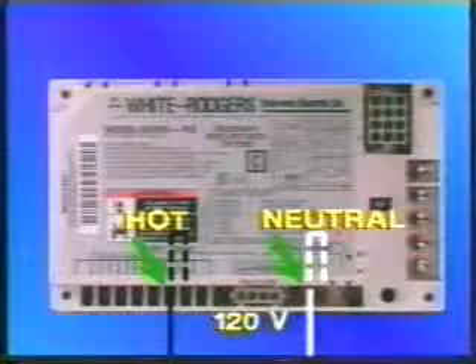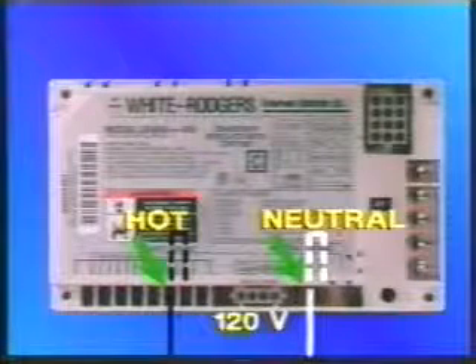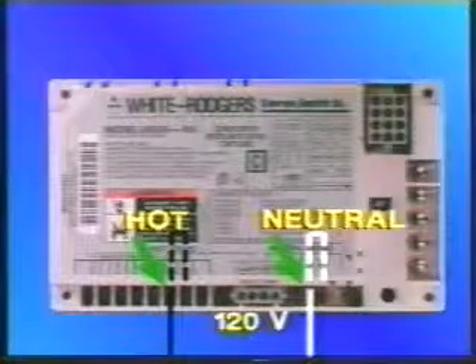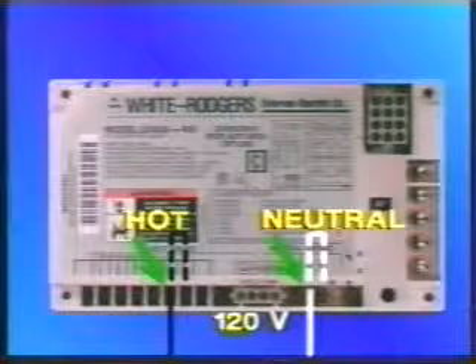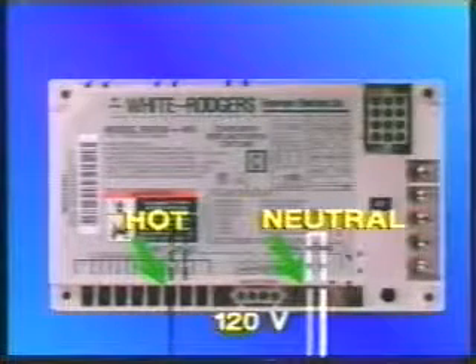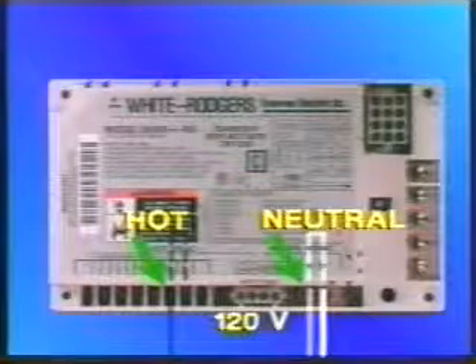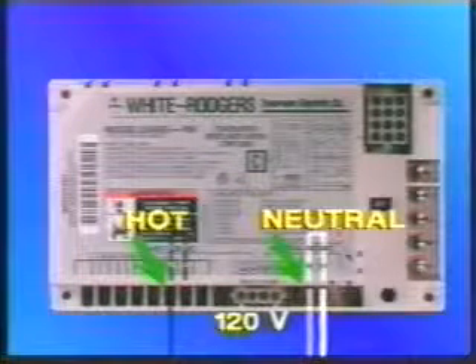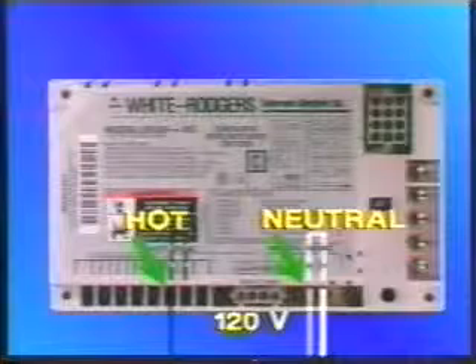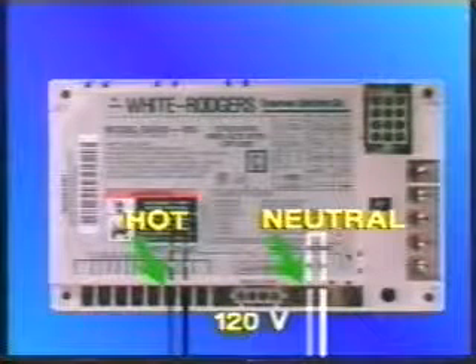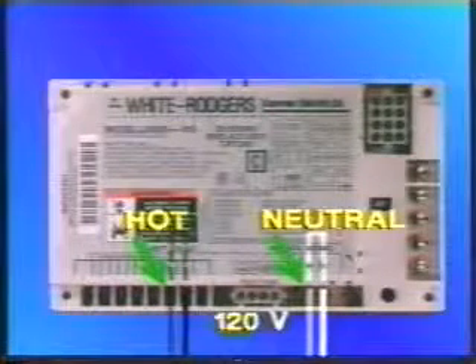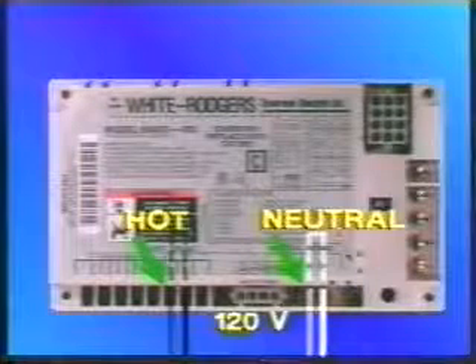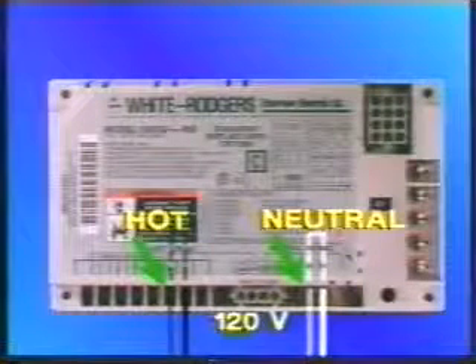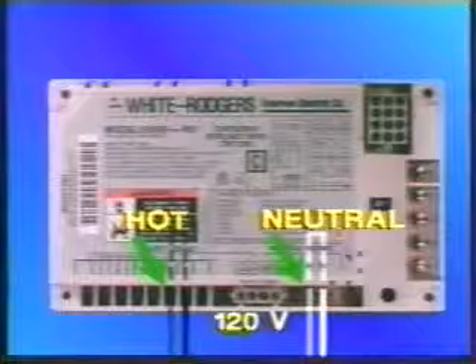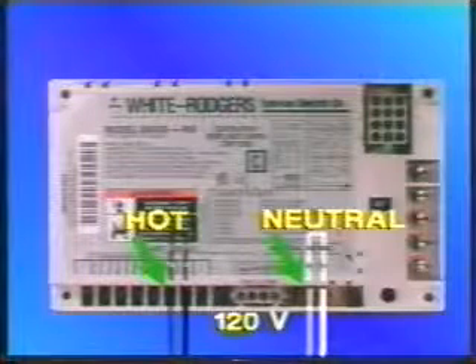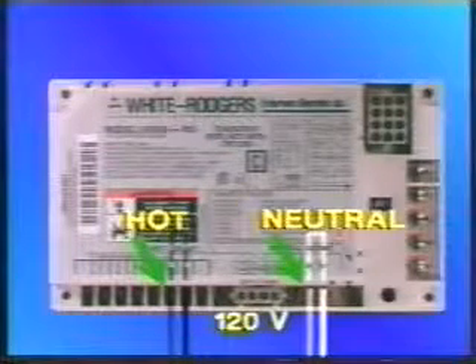The 120-volt line is routed internally to 2 terminals which power the primary side of the 24-volt furnace transformer. The neutral side of the 120-volt primary circuit is connected directly to the transformer neutral connection on the board. The hot side of the 120-volt circuit is connected to the hot transformer connection. It's important to note that these 2 terminals are at 120 volts line voltage to the transformer and are not an input from the transformer.